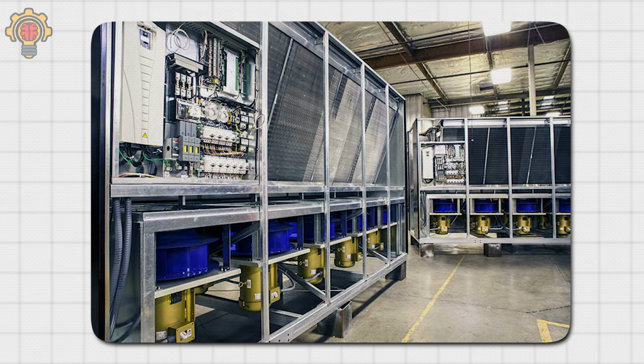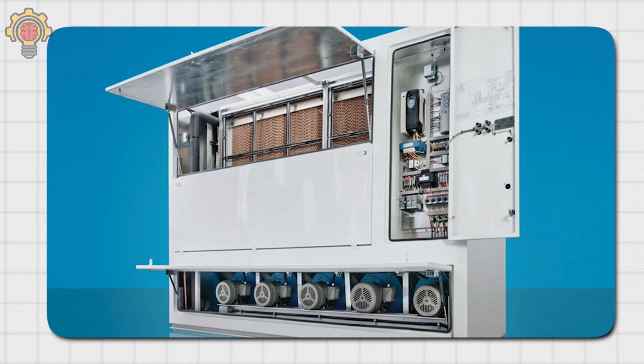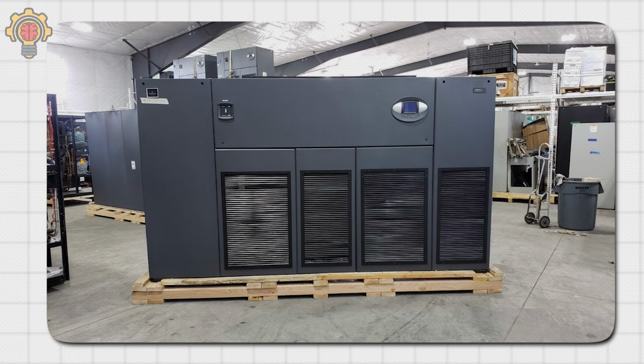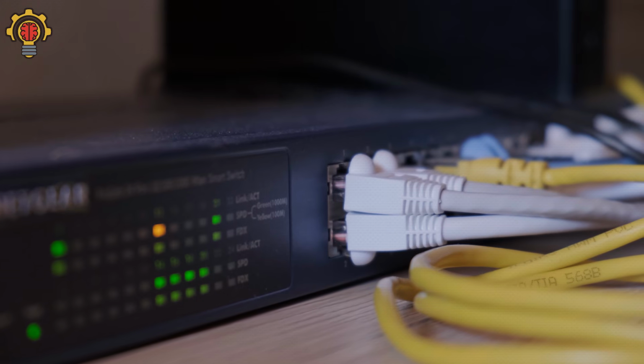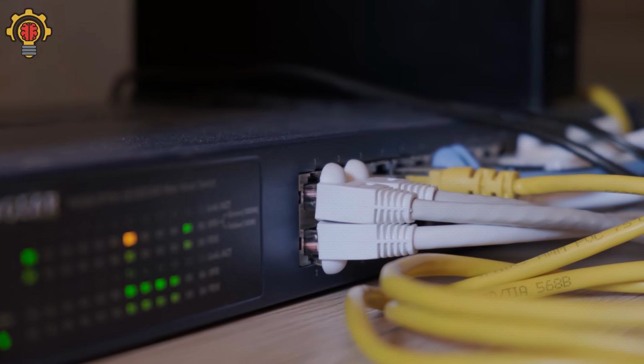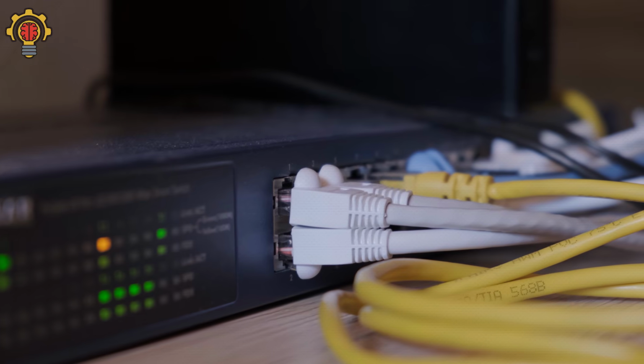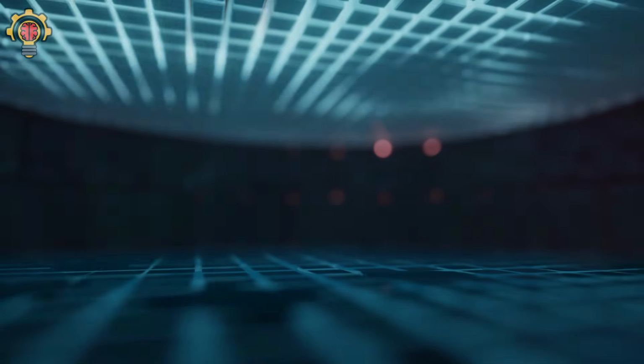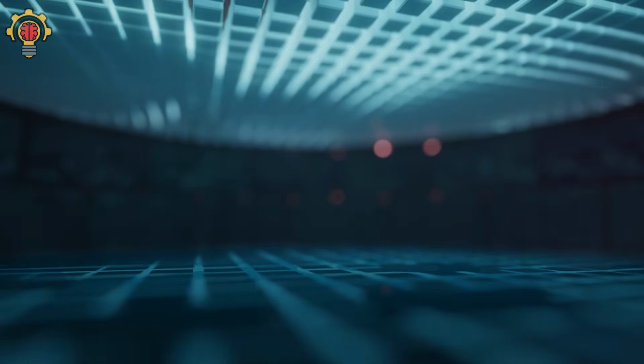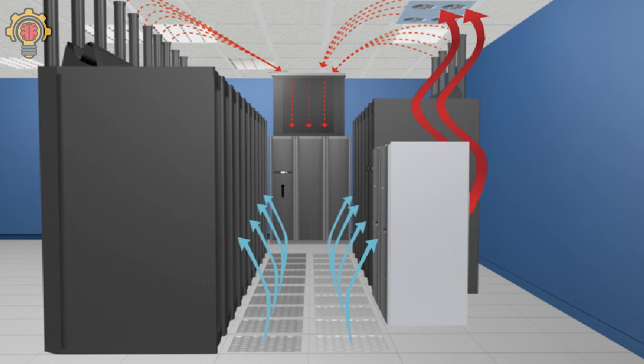A CRAH unit, or computer room air handler, uses chilled water flowing through cooling coils instead of refrigerant. That chilled water is produced by large chillers elsewhere in the facility. Both systems usually work with raised floor airflow designs. Cold air moves beneath the floor, rises through perforated tiles, enters the server racks, absorbs heat, then exits into the hot aisle before returning back to the cooling units.